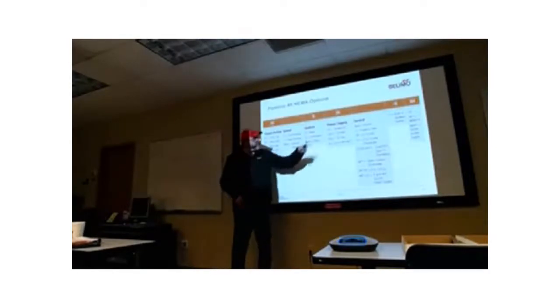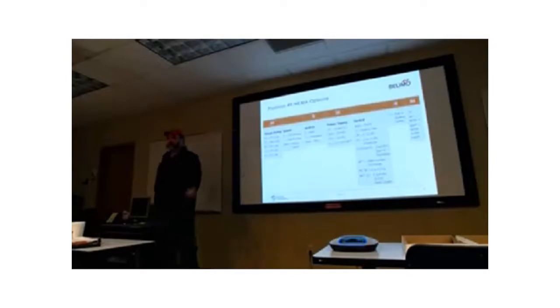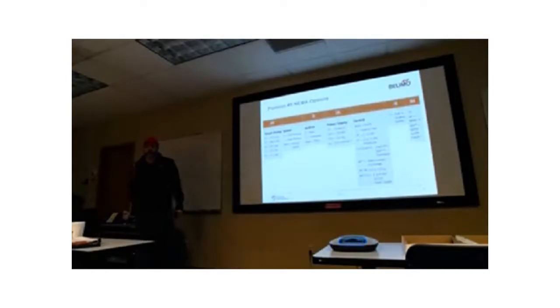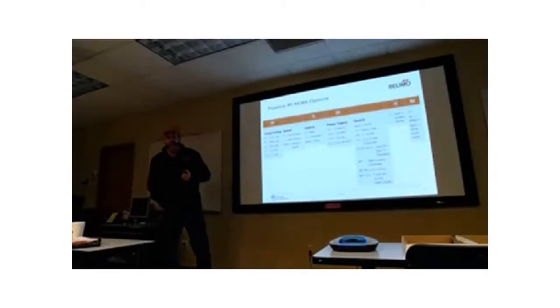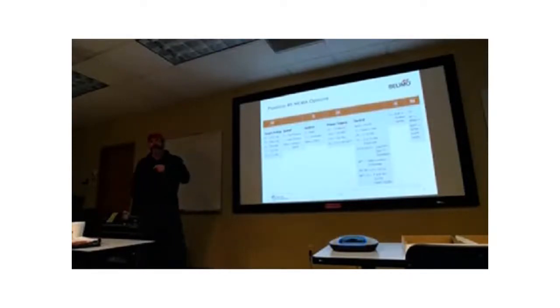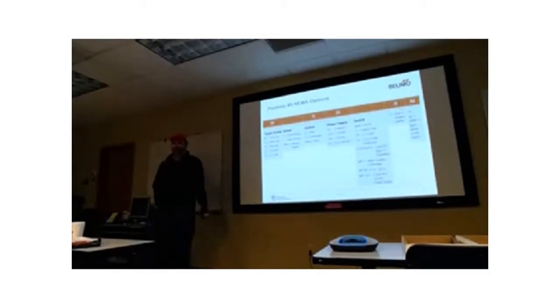We make a NEMA 4, and we make a NEMA 4H, which means you can get heaters put in these things. Around here we don't use them so much, but where would you use heaters? Alaska, right, Anchorage anyway. But you can also use them in Alabama -- why? For condensation. In Alabama you get condensing temperatures inside the actuator, so you keep the temperature up so you don't hit dew point inside the actuator.